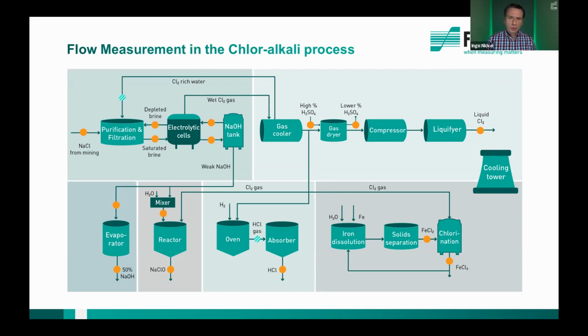For example, we are using one of our so-called PIOX systems to measure the supply of the raw brine, as well as the in and out flow of the treated brine in the chloralkali process. On the other end of the electrolyzer, the instrument is well adapted to measure the caustic soda in all its concentrations through the whole evaporation process. When it comes to other core processes within the chloralkali process, chlorine gas treatment, the main application is to measure the sulfuric acid for the chlorine gas drying, as well as the mass flow measurement of the liquid chlorine. Here you can see we are coming in contact with sulfuric acid and caustic soda, very aggressive media. If you have a measurement solution which is completely non-invasive, then it's a big advantage.